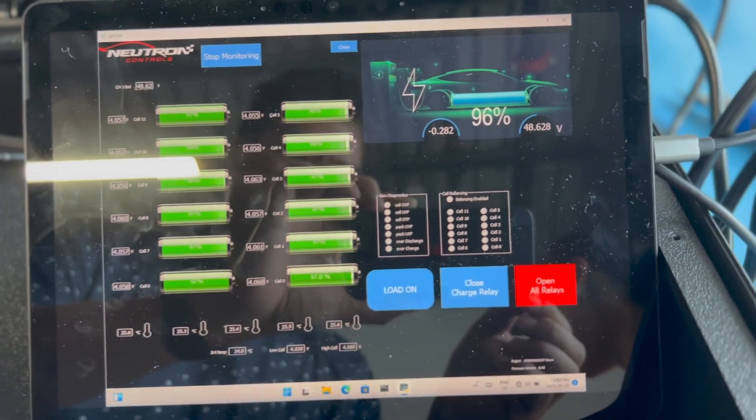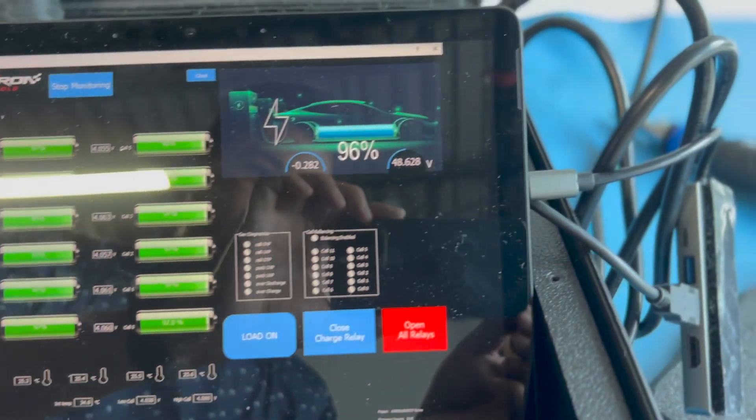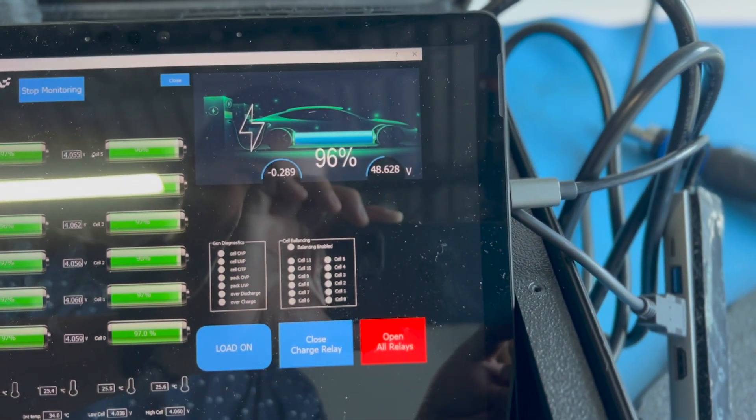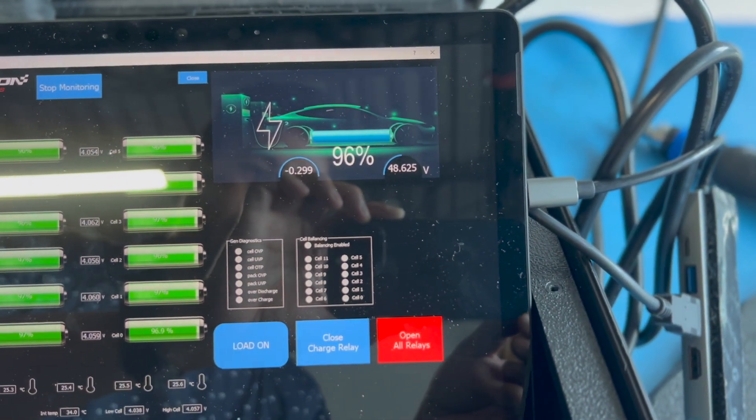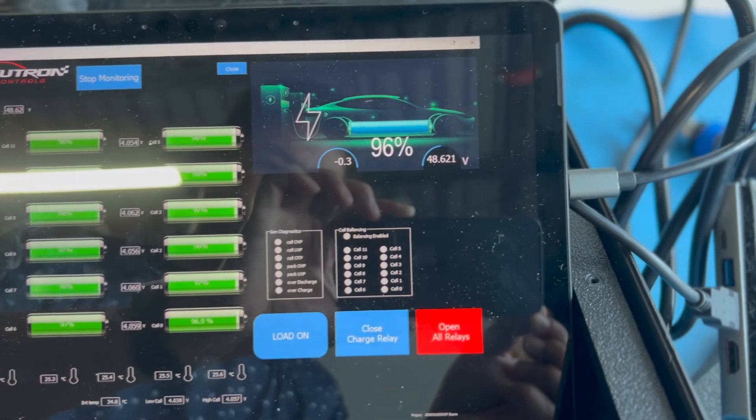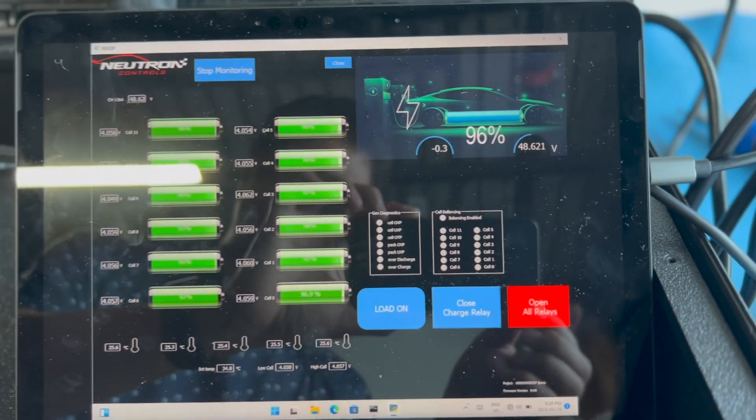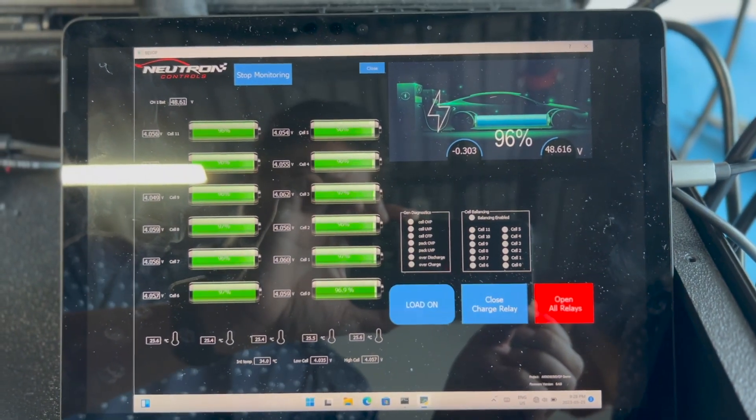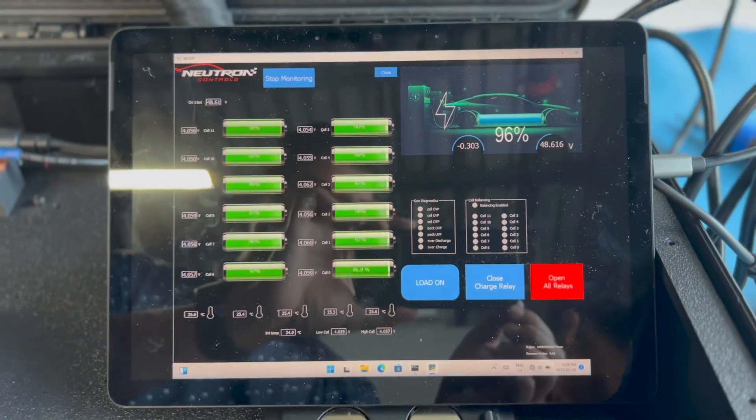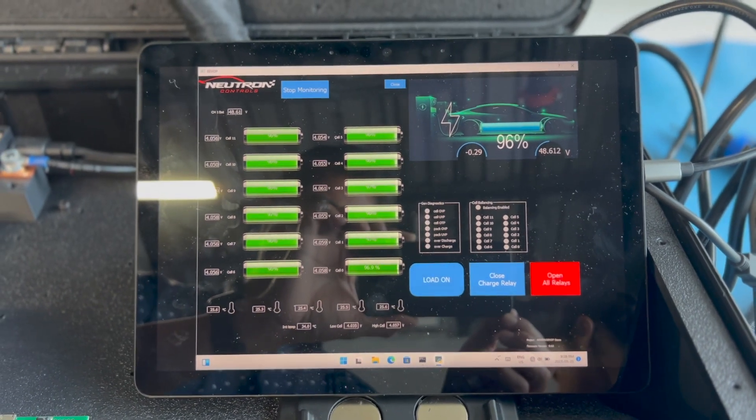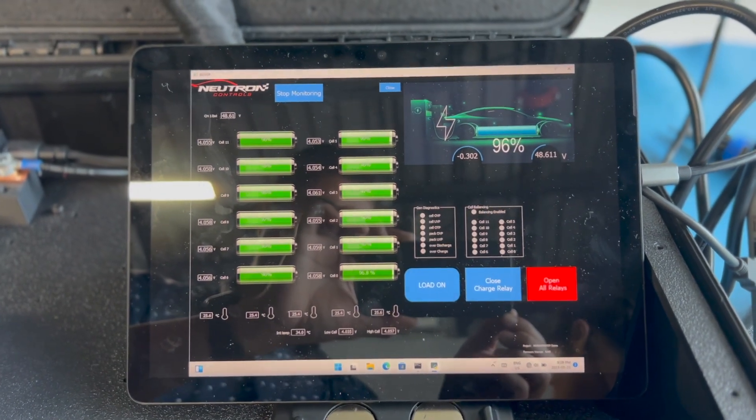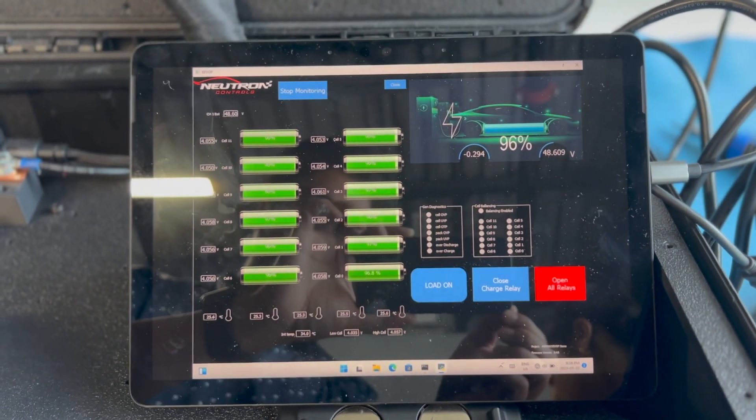On the GUI, there will be a reading for the current being depleted from the pack. Here, 300 milliamps draw is shown, which corresponds to what is set by the variable load. Depending on the current draw setting, the cell voltages will start to drop at relative rates. The higher the rate, the quicker the voltages will drop.